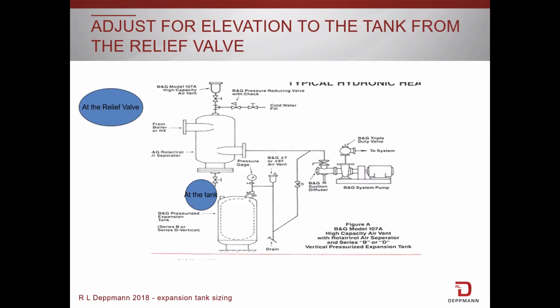In the previous examples, one of the items to consider was the elevation of the tank in relation to the relief valve. Gil Carlson from Bell & Gossett, who wrote the Engineering Design Manual, was fond of saying, a difference to be a difference has to make a difference. If the relief valve is within a couple of feet of the tank, you can consider them to be at the same elevation — there really isn't going to be enough pressure change to make a difference. Now, if the tank is at the top of the building, you definitely need to take that change in elevation into account.